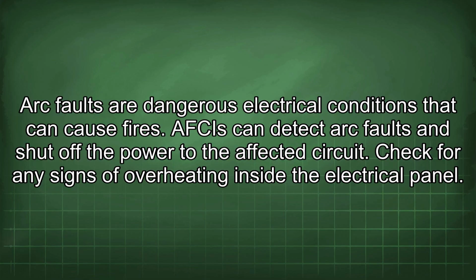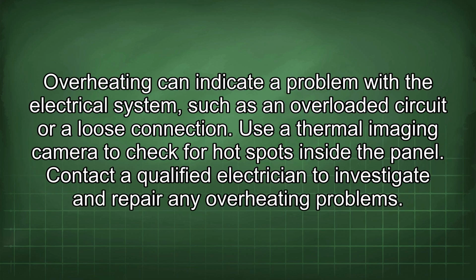Check for any signs of overheating inside the electrical panel. Overheating can indicate a problem with the electrical system, such as an overloaded circuit or a loose connection. Use a thermal imaging camera to check for hot spots inside the panel. Contact a qualified electrician to investigate and repair any overheating problems.